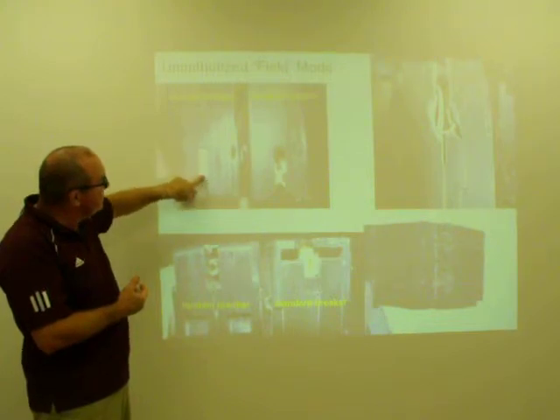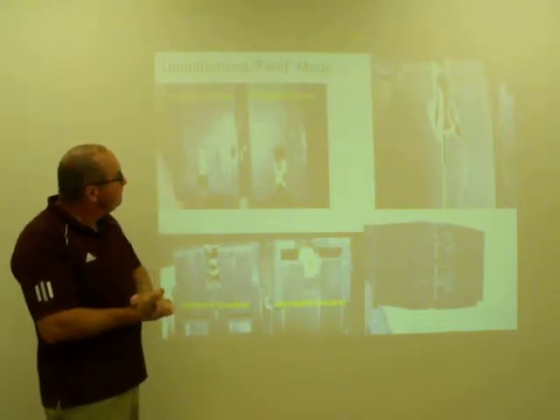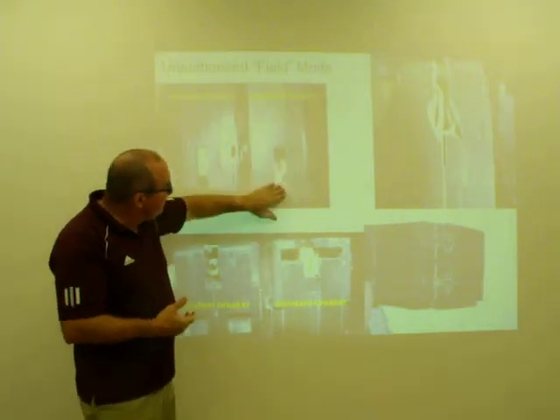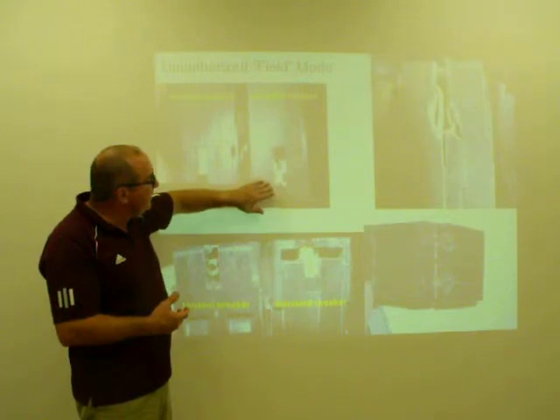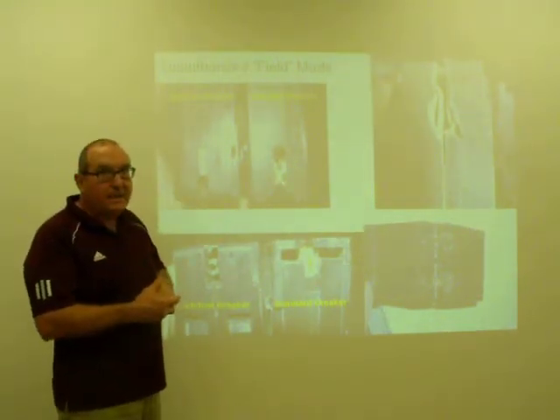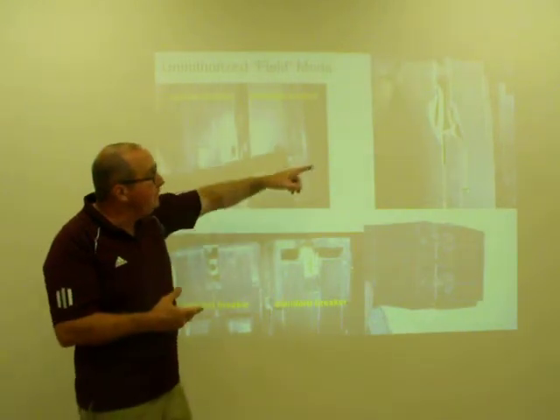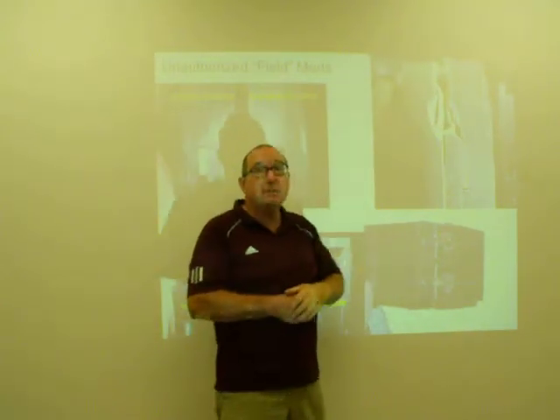So this tandem breaker has a metal piece in here that is designed to restrict where it can physically be installed. This standard breaker does not. Well, maybe they want to try to put this standard breaker in a space that's intended for a tandem or vice versa. So what do they do? They go in there and chip out the bakelite casing on this molded case breaker so they can make it fit.